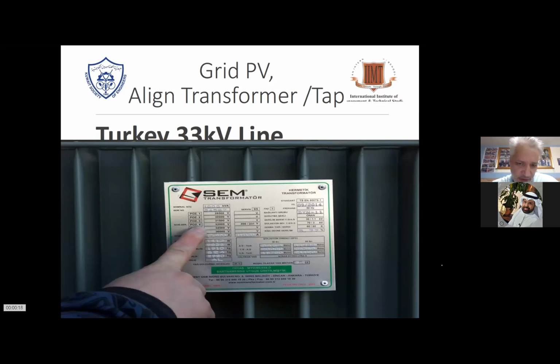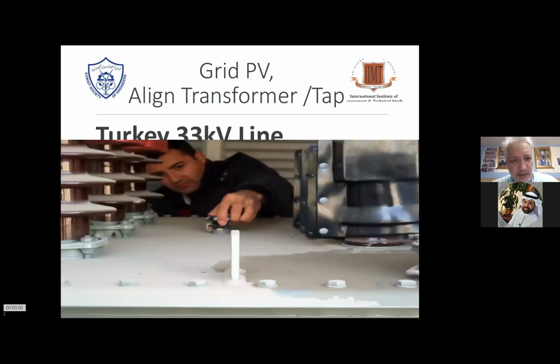So it depends on what you find on site. If your system is very high on the low voltage side, like 400 volt, 420, then you pull it down to 400 volt, and you vary it with the existing tap settings. I think I have a picture. Yes, that's for example a tap setting. So you de-energize, of course. You go to the settings. You put it from 1 to 5. Normally they get delivered with setting number 3. Here you put it either to number 2 or to number 4. And then you will find out a different scenario. Either the voltage will increase or decrease, depending on what problems you encounter on the site.